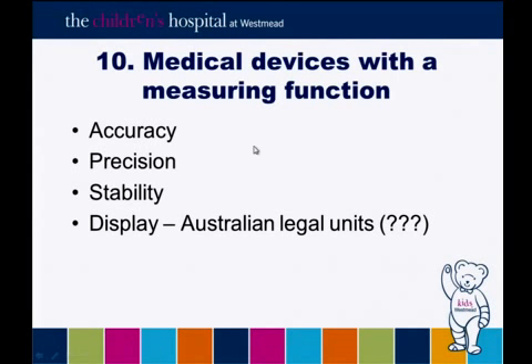The essential principle 10 for medical devices is medical devices with a measuring function. We all know about accuracy: if something's a metre long and you measure it, it says that's a metre long. Precision is how fine you can break that down, so is it measuring within 1 millimetre or 1 micrometre? These are standard engineering terms that apply everywhere. Then there's stability, which is how long it stays without drifting off measurement. And then there's an interesting one, which is the display, and everything should be in Australian legal units.